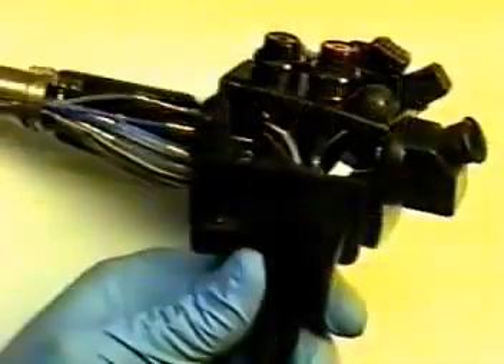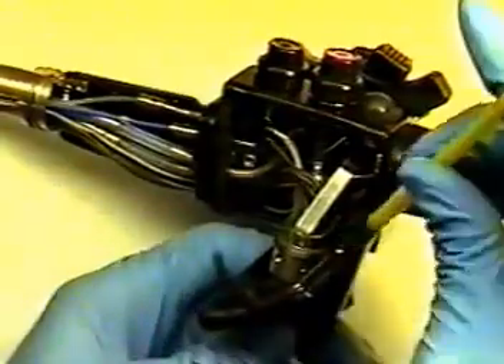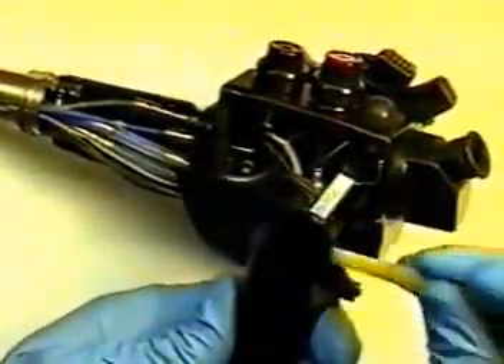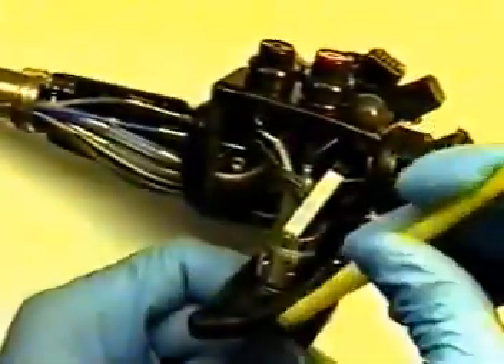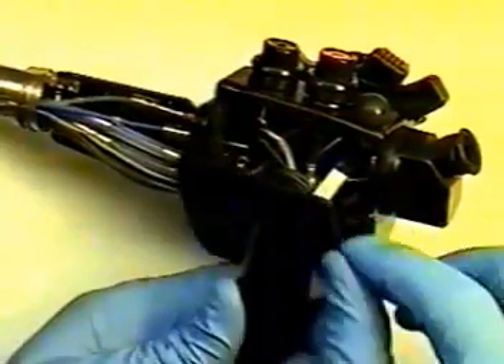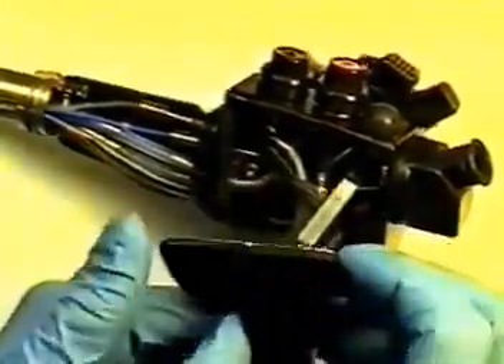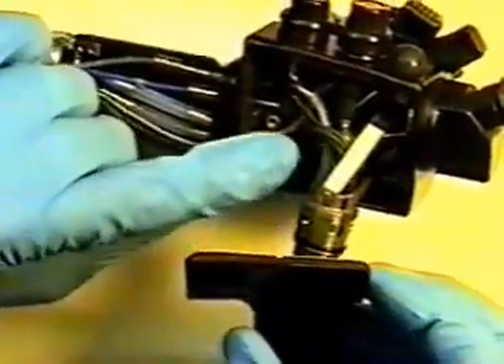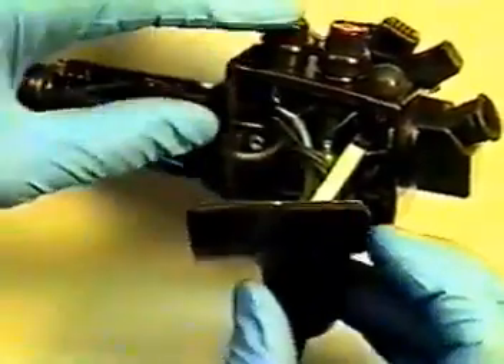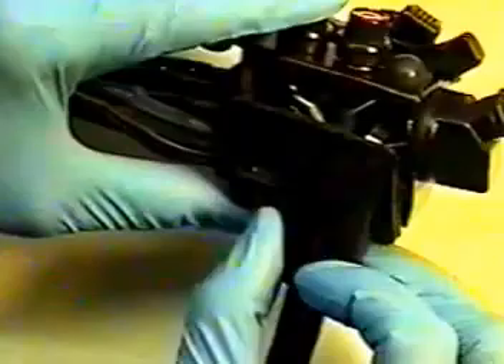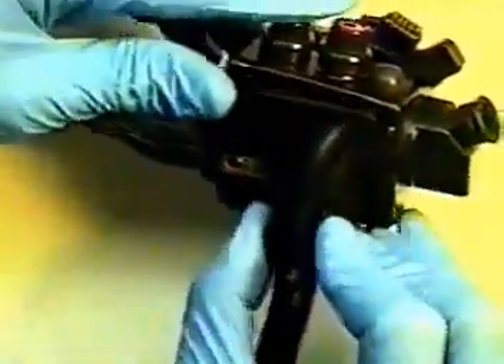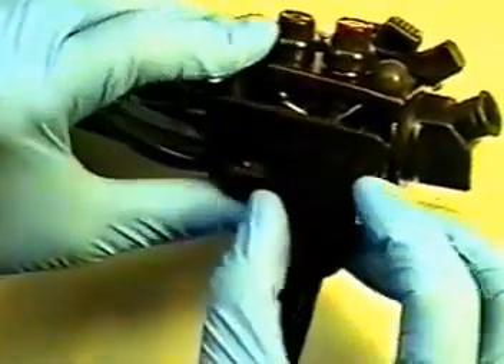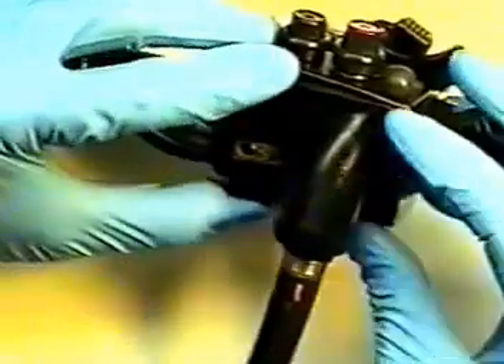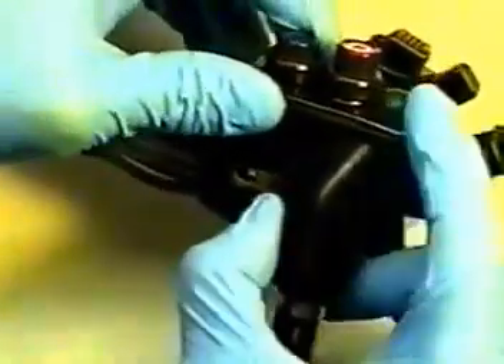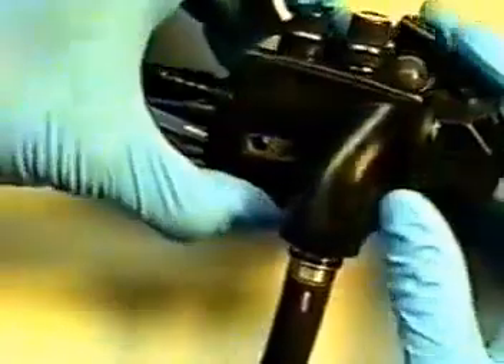First, pull up side body cover. If you have a small paintbrush, some white lithium grease, clean around the O-ring to make a proper seal. Making sure that all the wires, light guides, and channels are all fit inside body section, you can pull up body cover, side cover. Carefully latch top tongue to meet underneath lip and push down to seal O-ring.